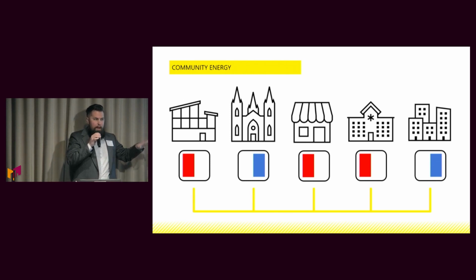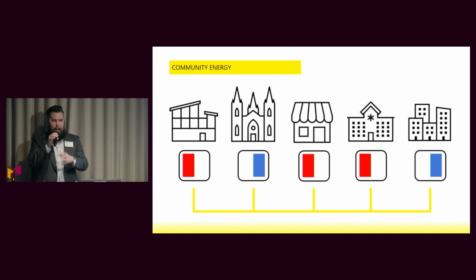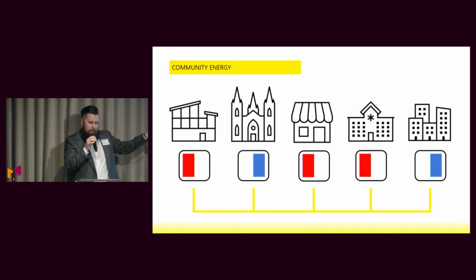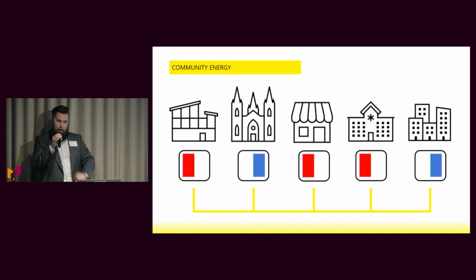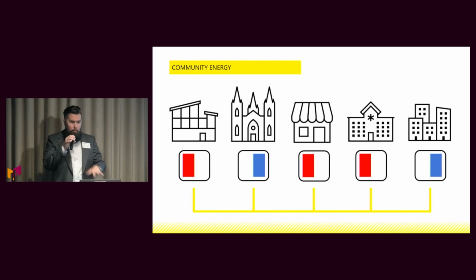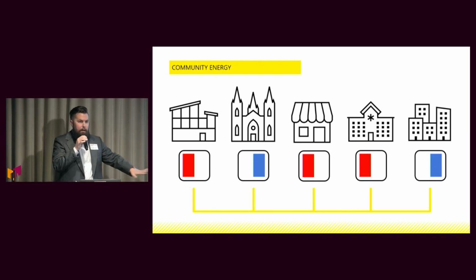By using the magic of a heat pump, I can suck the heat out of that warm water and condense it down, so now we have high-grade heat that's much hotter that I can use to heat the building. Rather than stealing heat from the air, I'm stealing it from this warm water. Or if I have a building that's cooling off, I can dump heat into that warm water rather than out to the air, which is more efficient. So I can move that heat into the water, and now it's in a platform where others can tap into it and use that energy.